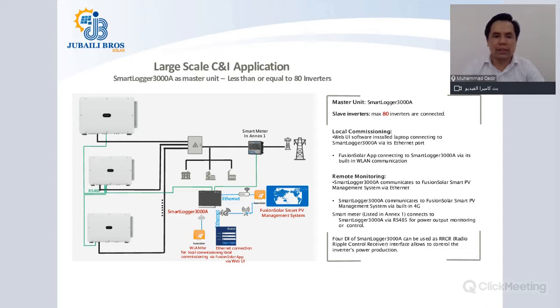Okay, so in the large scale C&I application where you are using the Smart Logger 3000A as master unit, you will have less than or equal to 80 inverters. As I said, the Smart Logger can connect up to 80 devices, so you have the option of connecting a maximum of 80 slave inverters.